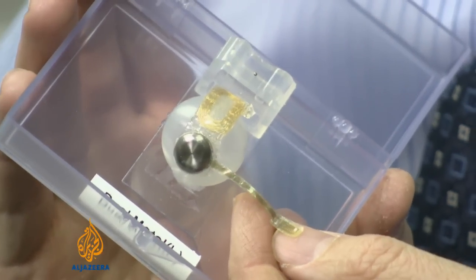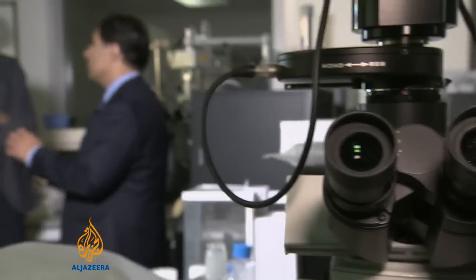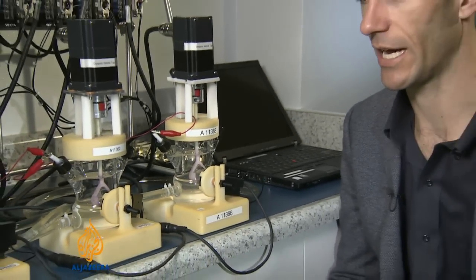The tiny implant requires manual assembly under a microscope, which helps to drive the price to $145,000. The FDA required the company to build a test which simulates the warm, wet, salty conditions of the eye. The company intends the implants to be permanent, but they're really only rated for five years. It's a real question of just how long this remotely powered combination of titanium, platinum, and silicon is going to last inside the body before it needs replacing.